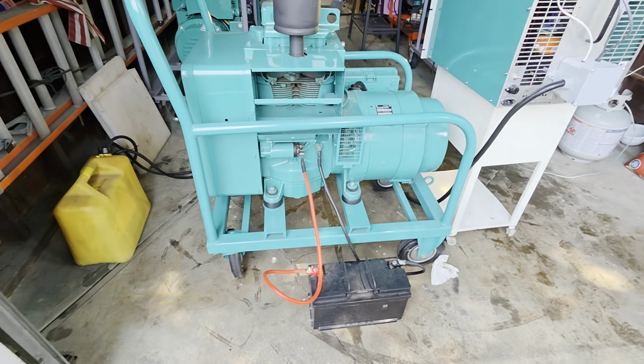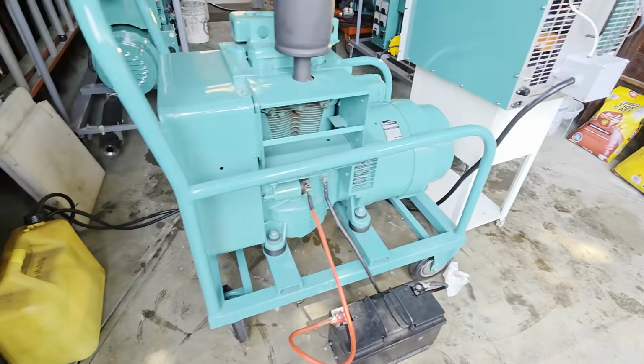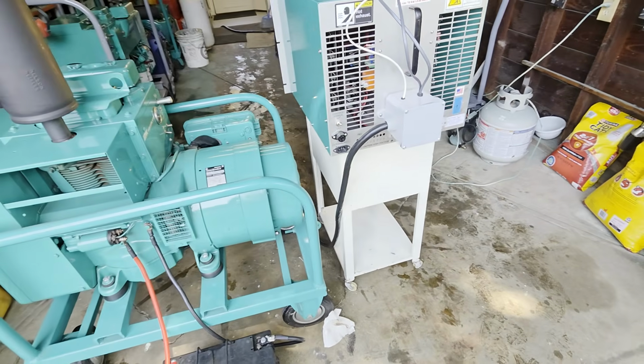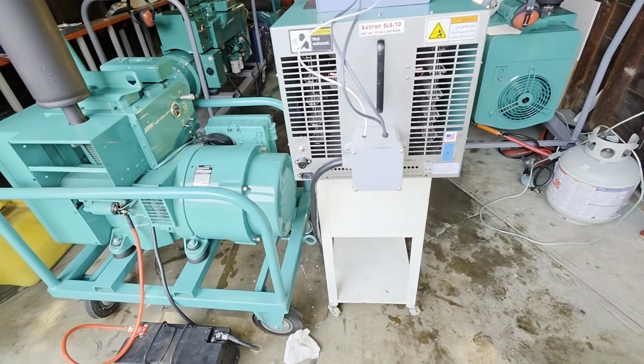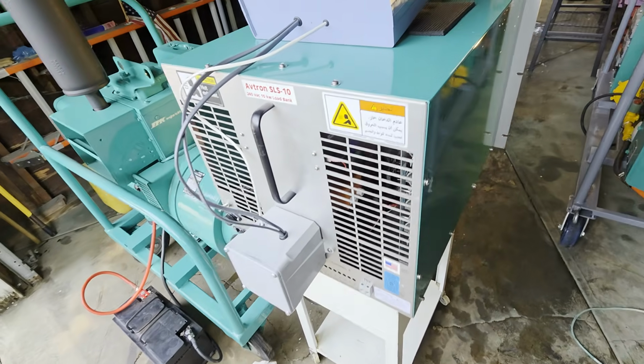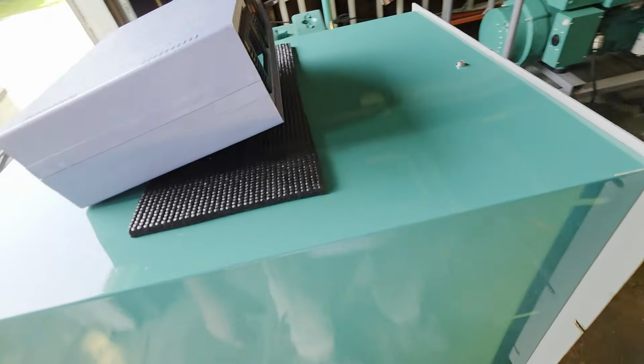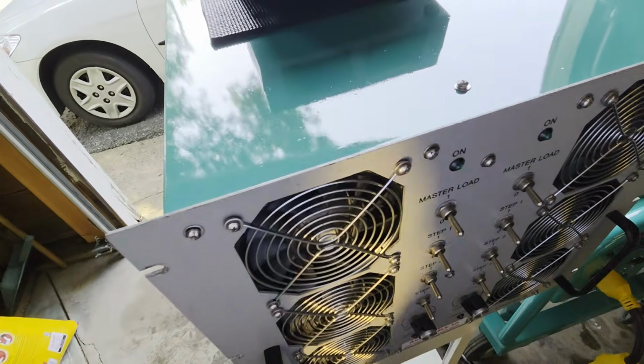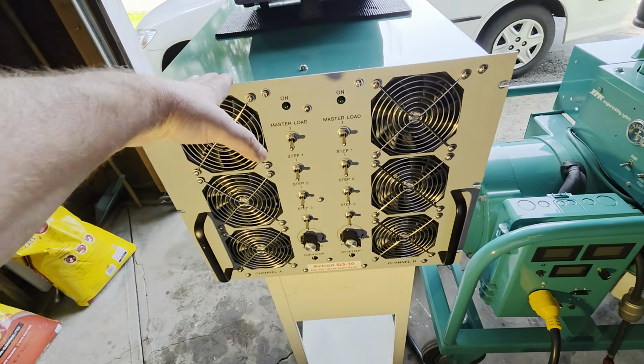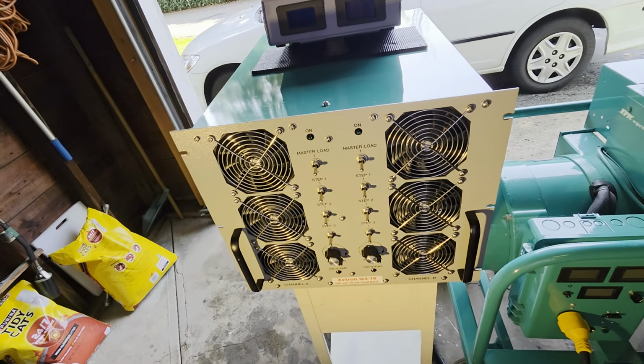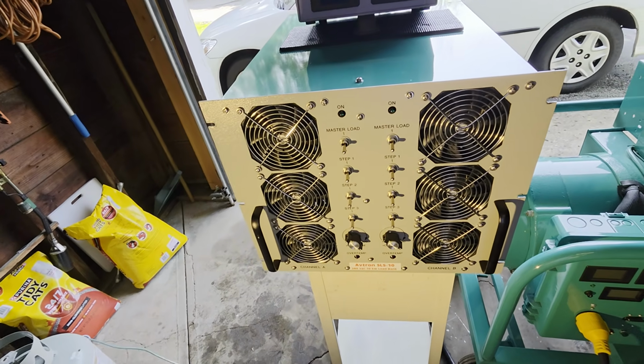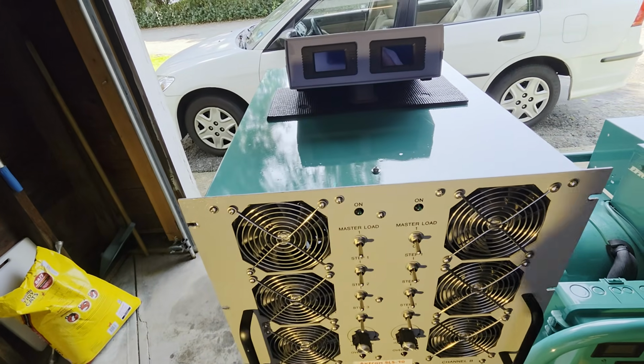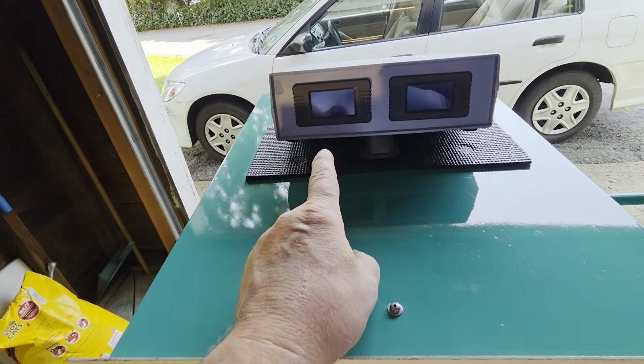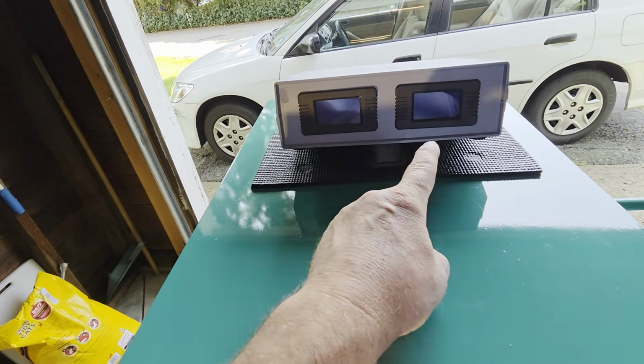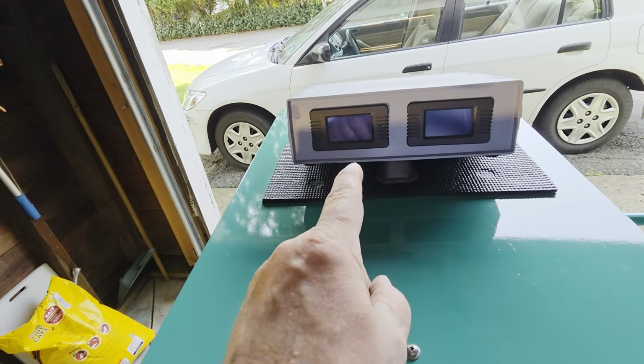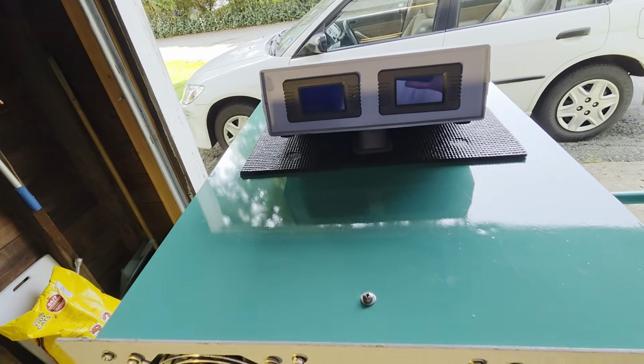So you see the setup we've got here, it's very simple. Once I start it up, it's very loud, you won't be able to hear me all that well, but I'll try my best. Basically, I'm going to adjust the load bank for about a 5-6 kilowatt load, roughly, maybe a bit more, and we'll verify it on the meters, which show both legs. We'll be running 240 volts, so roughly 120 per leg.